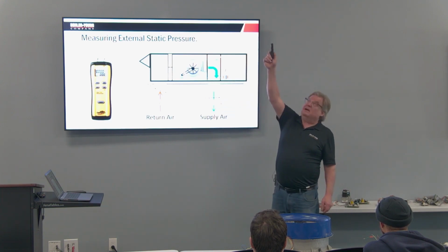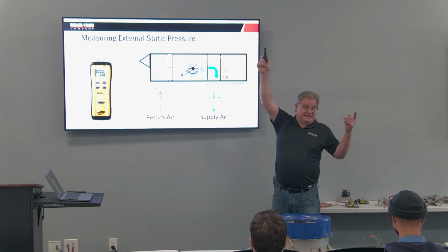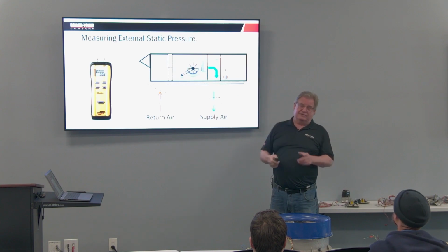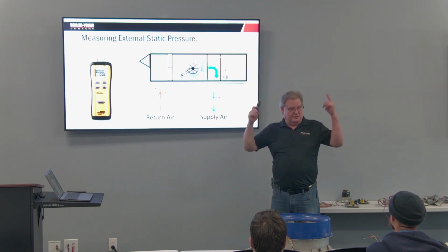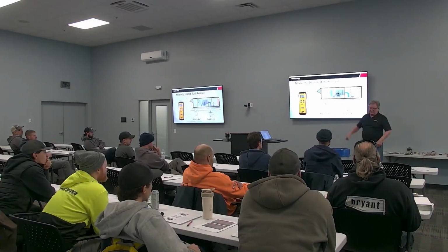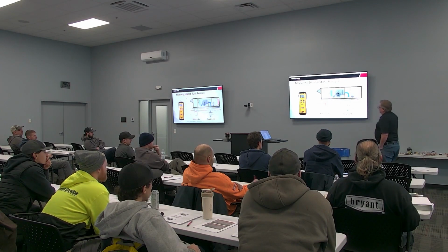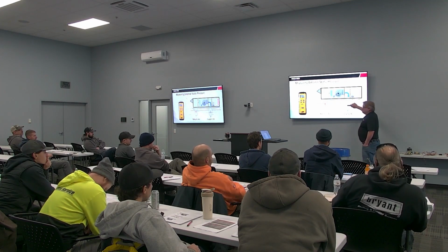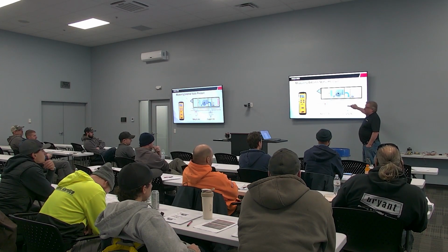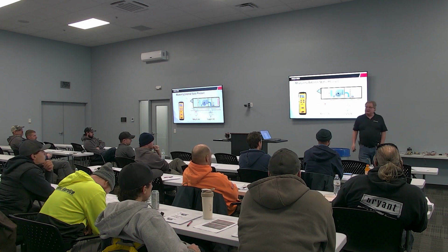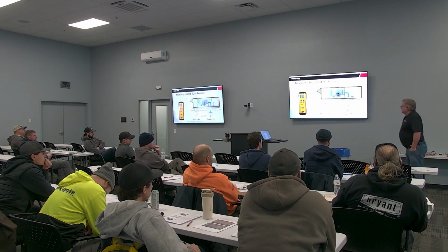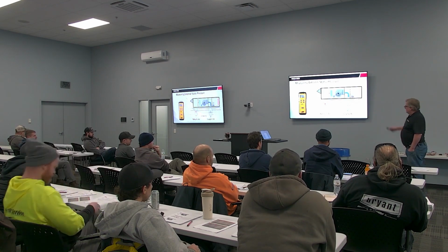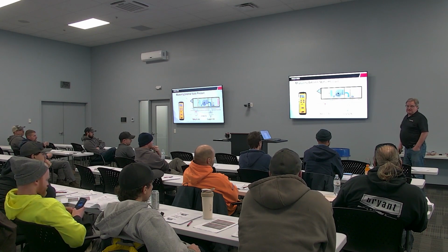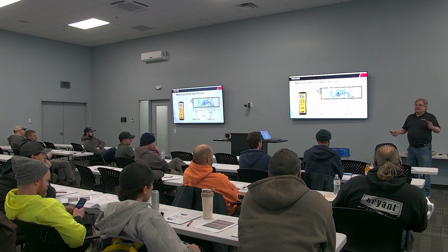Okay, now my ductwork's above the ceiling here. This is not easy to get to. So ideally, new construction especially, you want to do it when the unit first goes in, when you can get to it. Okay, so in the return and the supply drops. We got to get into the drops, not into the unit. Those readings will not be correct. So I got 0.4 on my return, 0.5 on my supply, drop the negative, drop the positive, add them together, 0.9. So we have 0.9 inches of static.